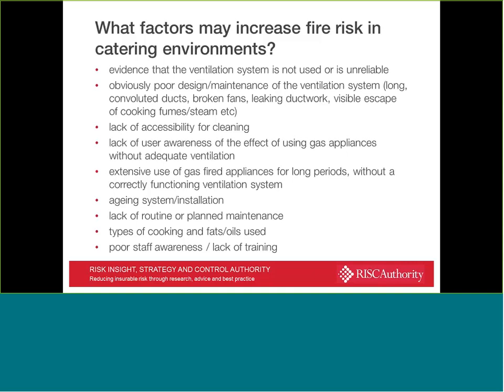Cooking oils, if they're repeatedly used, will over time oxidise, which reduces their flash point. So you may have an oil which traditionally will have a flash point of between maybe 200 and 300 degrees, but over time the flash point will reduce quite significantly, which means it's more likely to combust, particularly if thermostatic controls aren't in place, or alternatively there are other sources of ignition nearby.